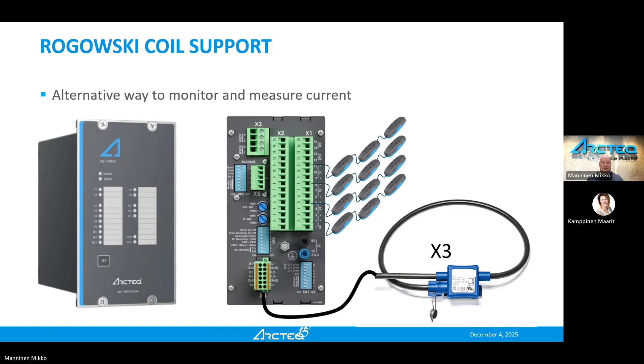Let's move on. About Rogowski sensors and the units. The AQ110 device, I call it, the so-called main unit, supports three different secondary coil options, millivolt options. So how Rogowski works: it measures the current and the output is millivolts. It can be selected in the relay to 22.5 millivolts per 1 kiloampere, 100 millivolts, or 333 millivolts per 1 kiloampere. These options are available for all main units, including both the point sensor units and the fiber optic versions in low voltage and medium voltage solutions.